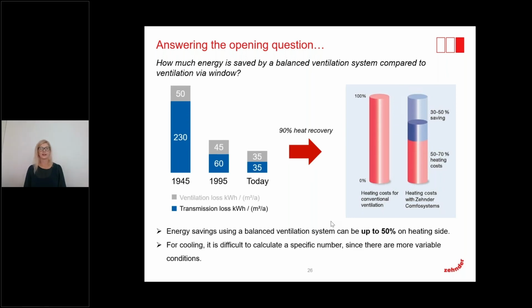For cooling, on the other hand, it is difficult to calculate a specific number for what the costs would be for the cooling that is recovered, since there are more variable conditions there. Let's say humidity plays a huge role, and also air volumes, and that makes it more difficult to give a concrete answer. But overall, with heat recovery around 90%, we could save up to 50% on the heating side.